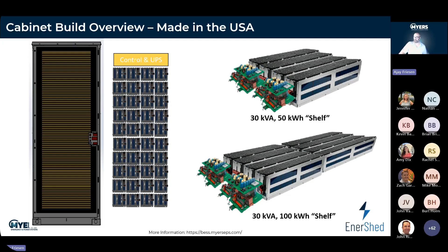We're also a step ahead when it comes to the fire safety of the energy storage system. So EnerShed 2.0 will comply with the latest NFPA 68 and 69 standards. Those are ones that AHJs have just started to ask about somewhat recently. Certainly in California they're starting to, and in other areas of the country. Those are explosion and deflagration standards that EnerShed 2.0 will meet, as well as the new NFPA 855 standard. There was a new NFPA 855 standard that dropped just at the end of last year. EnerShed 2.0 will meet that.